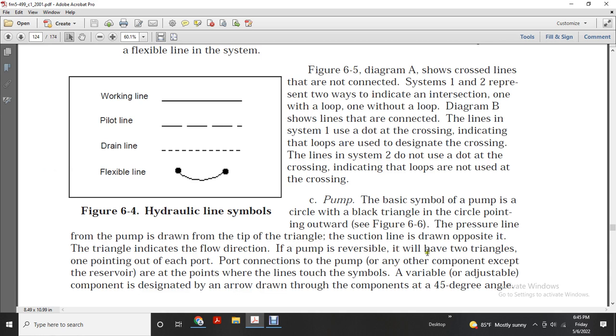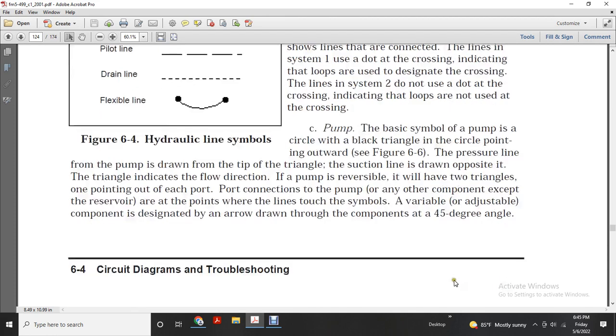If the pump is reversible, it will have two triangles, one pointing out of each port. Port connections to the pump, or any other component except the reservoir, are shown at the ends of the line touching the symbol. Variable or adjustable components are designated with an arrow drawn through the component at a 45-degree angle.